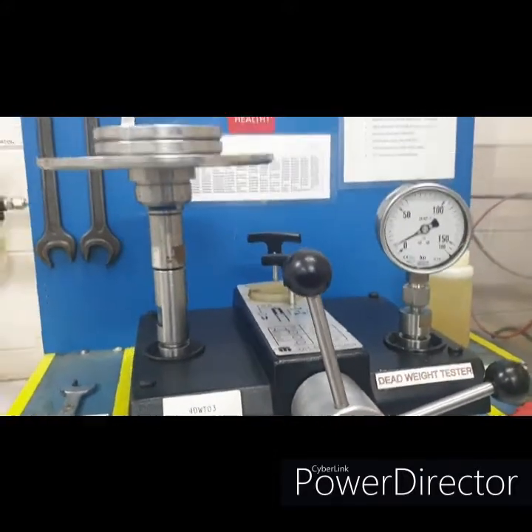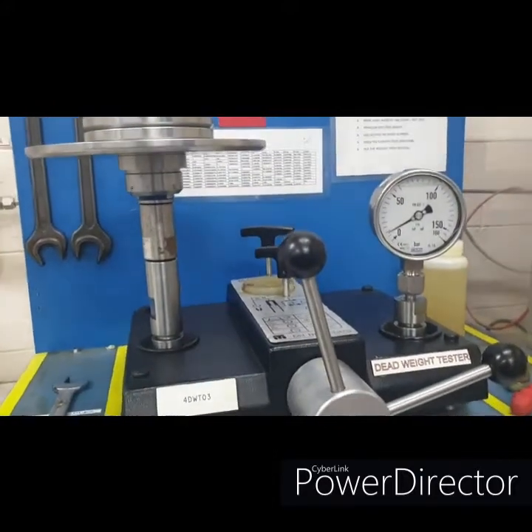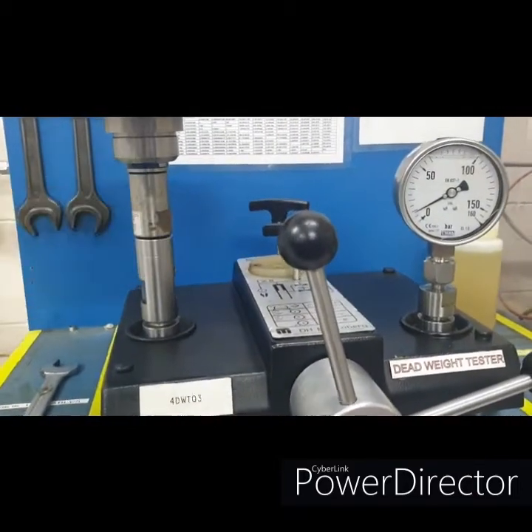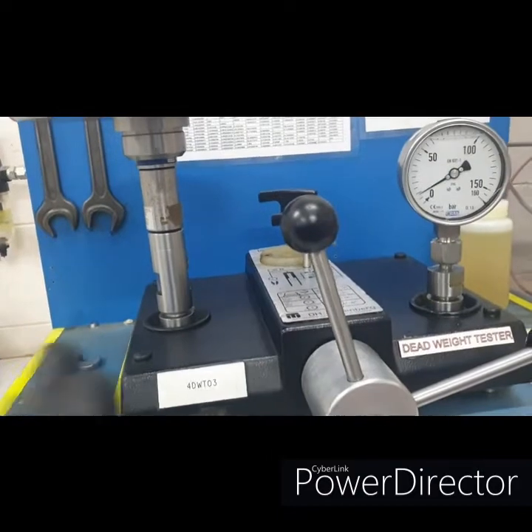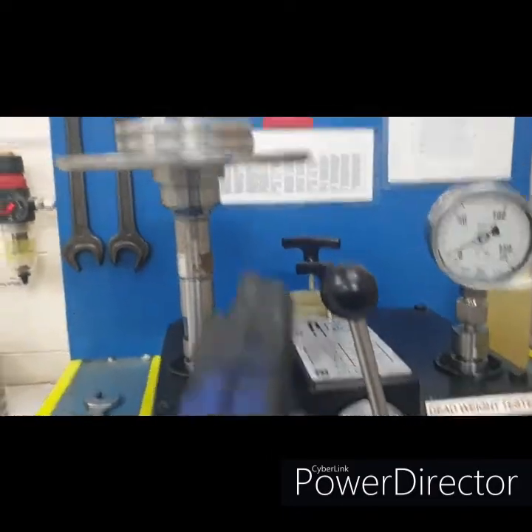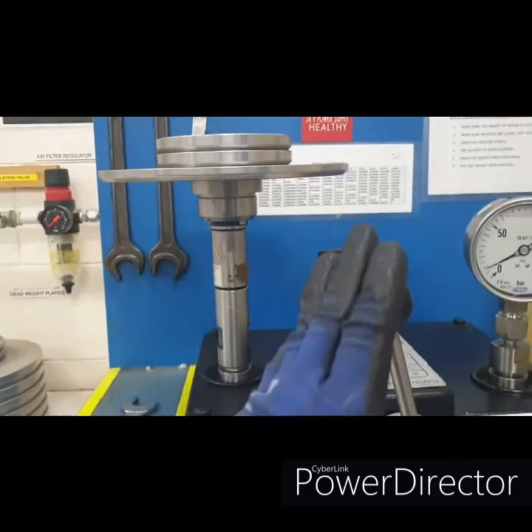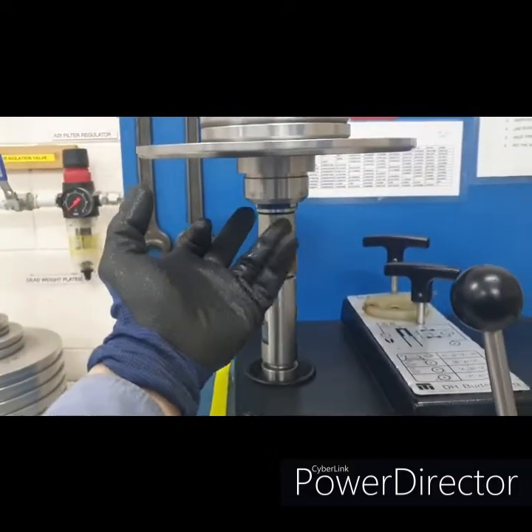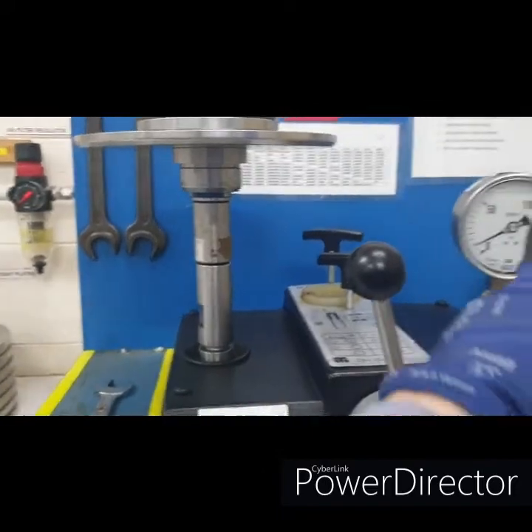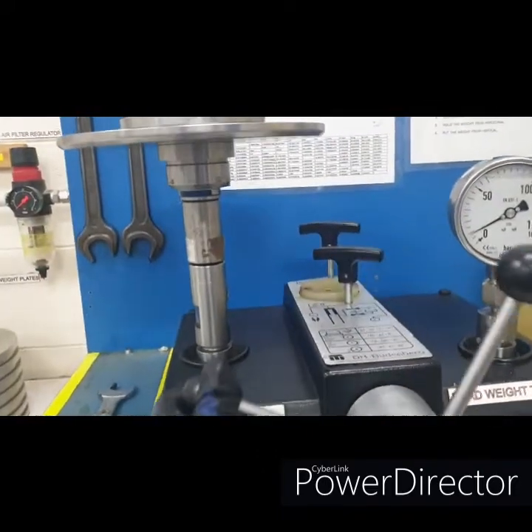So 10, this is the low pressure. Now, we will apply higher pressure since this is 10 and the higher pressure, the red indicator, that is times 10. So 10 times 10, it would be 100. I will apply 100 bar with the same weight. We're going to expect that the piston will displace up to the red indicator and it will indicate the gauge at 100 bar.